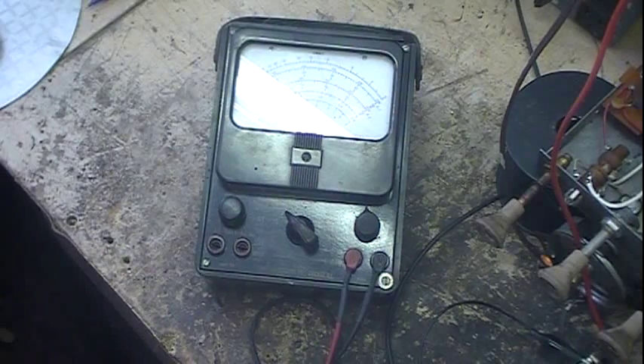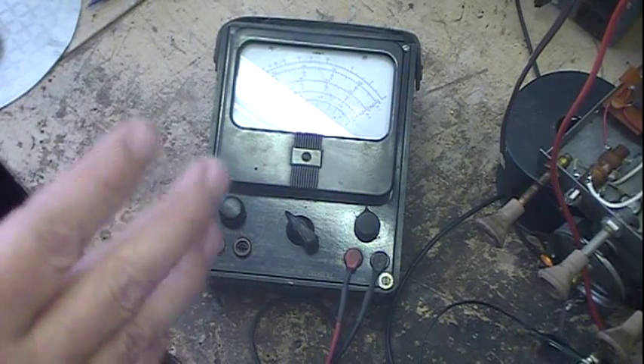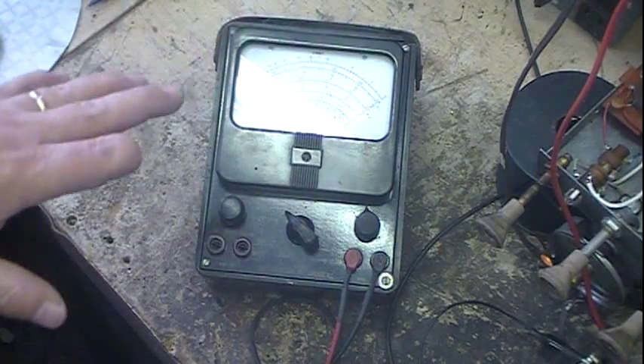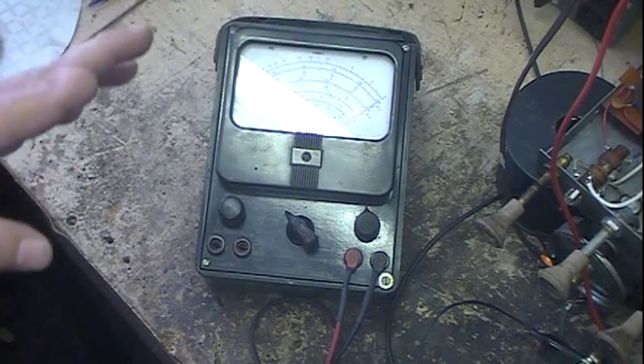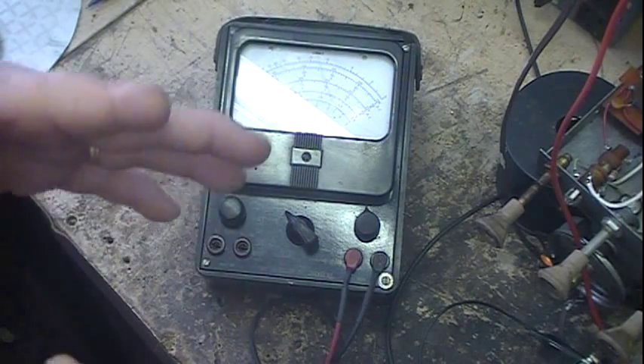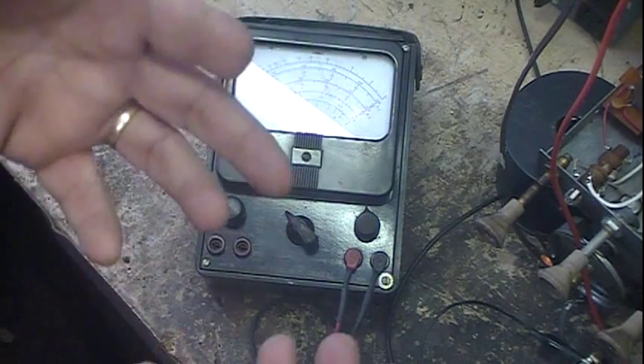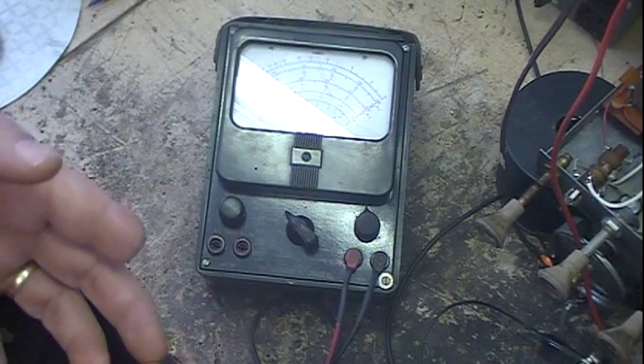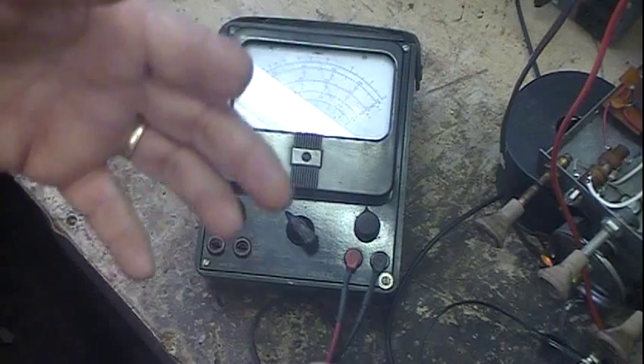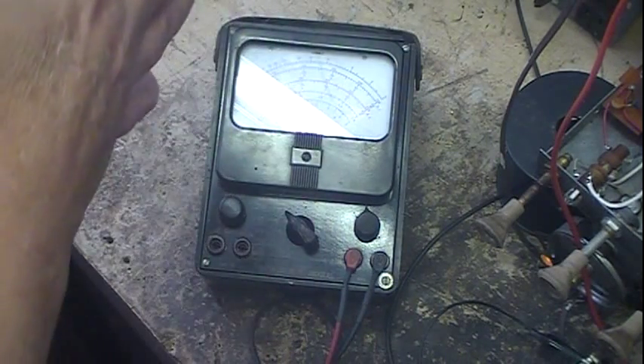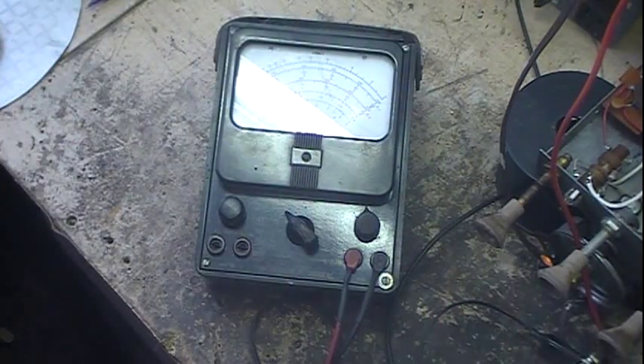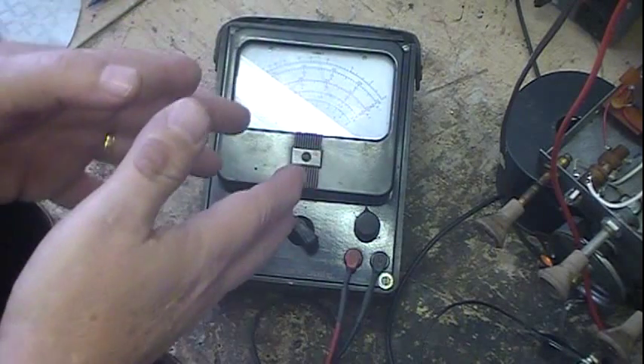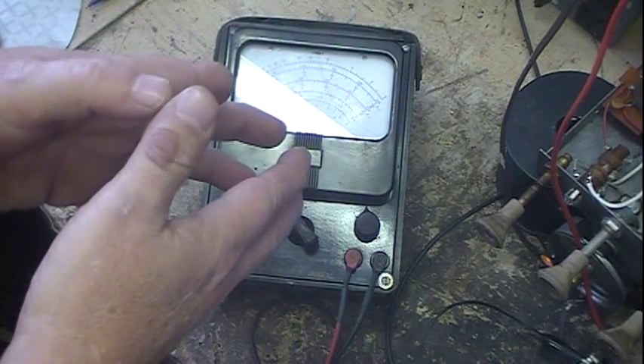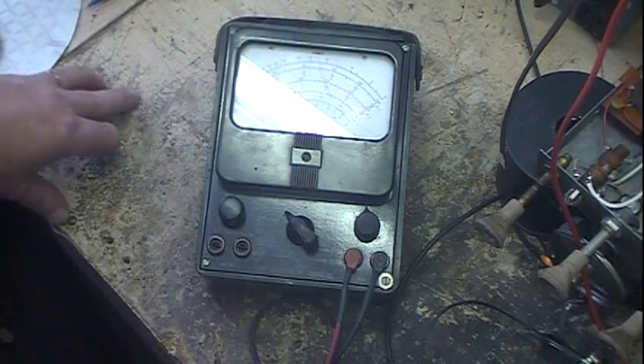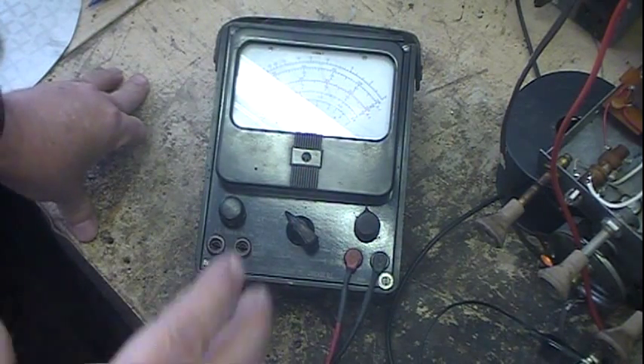So what's the deal? Well, the deal is simply this: the isolation transformer is doing its job, and it's working. It's isolating. But when I put a 10 megohm meter on it, it doesn't load the circuit very much, and at that point this thing is radiating out energy. The outlet radiates out energy. It's AC - even though it's 60 cycles, it's still an AC transmitter antenna, and that's what the meter is actually picking up. That's what it's seeing.